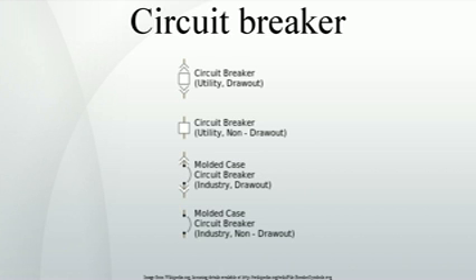High voltage circuit breakers. Electrical power transmission networks are protected and controlled by high-voltage breakers. The definition of high voltage varies, but in power transmission work is usually thought to be 72.5 kV or higher, according to a recent definition by the International Electrotechnical Commission, IEC. High voltage breakers are nearly always solenoid-operated, with current-sensing protective relays operated through current transformers. In substations, the protective relay scheme can be complex, protecting equipment and buses from various types of overload or ground earth fault. High-voltage breakers are broadly classified by the medium used to extinguish the arc.